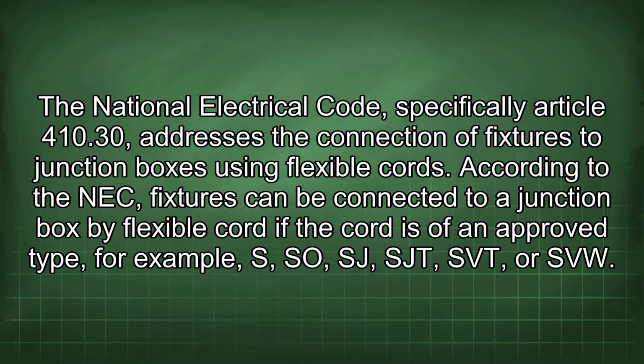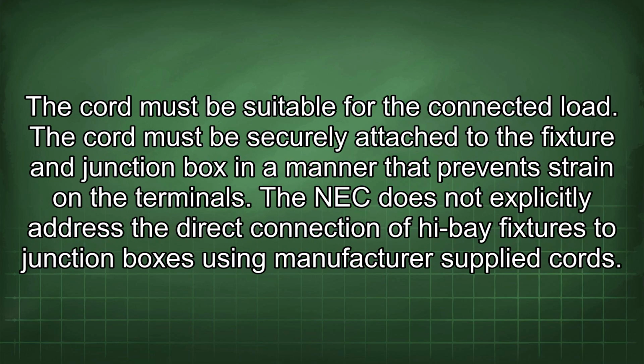The National Electrical Code, specifically Article 410.30, addresses the connection of fixtures to junction boxes using flexible cords. According to the NEC, fixtures can be connected to a junction box by a flexible cord if the cord is of an approved type, for example SO, SJ, SJT, SVT, or SVW. The cord must be suitable for the connected load.